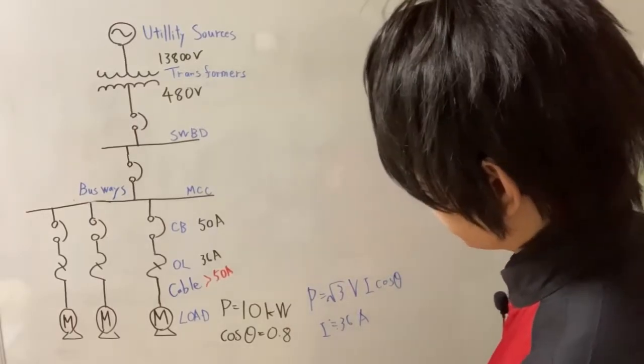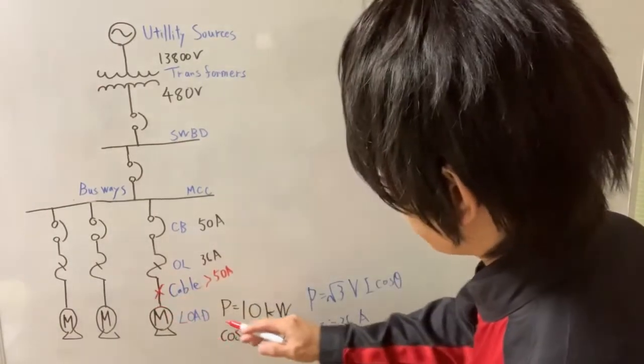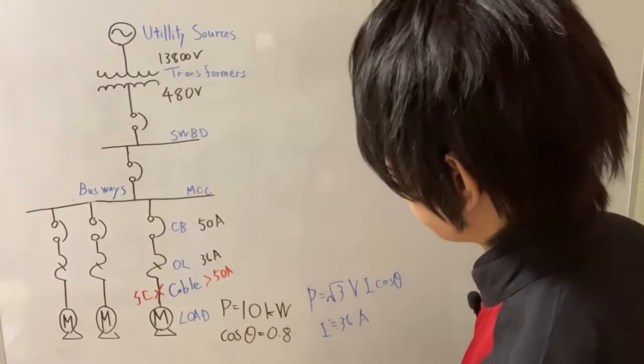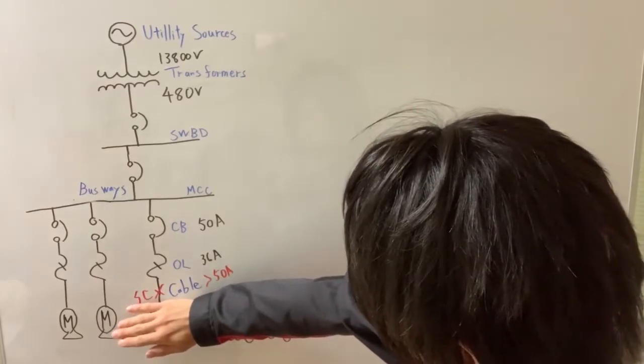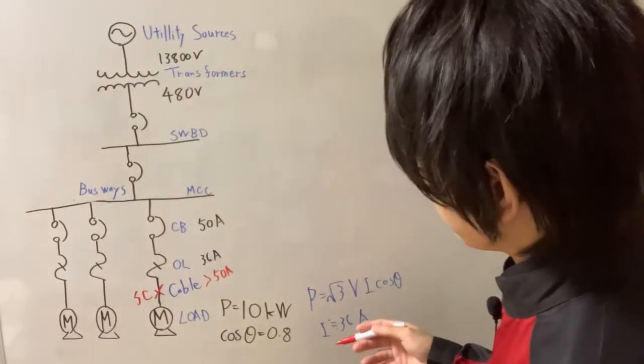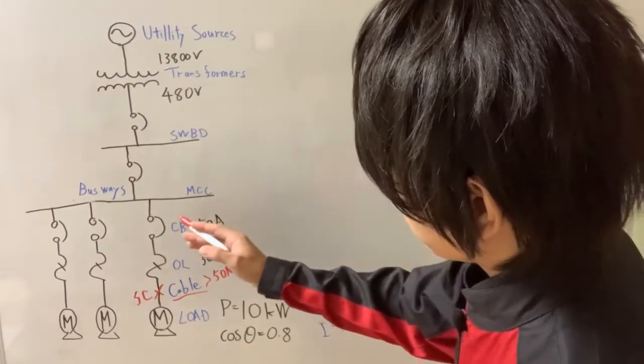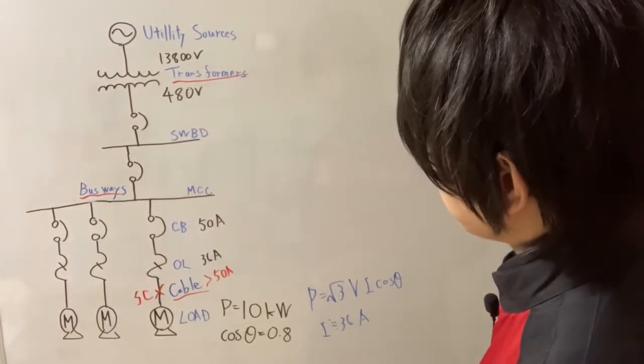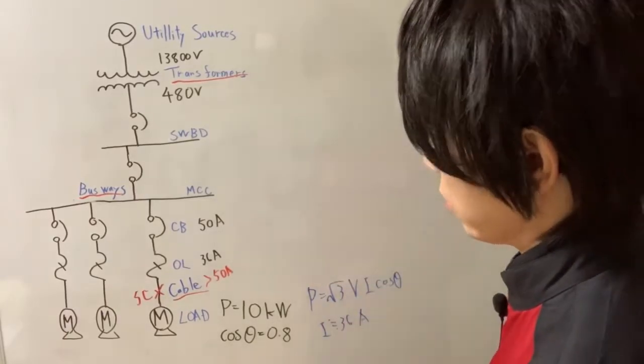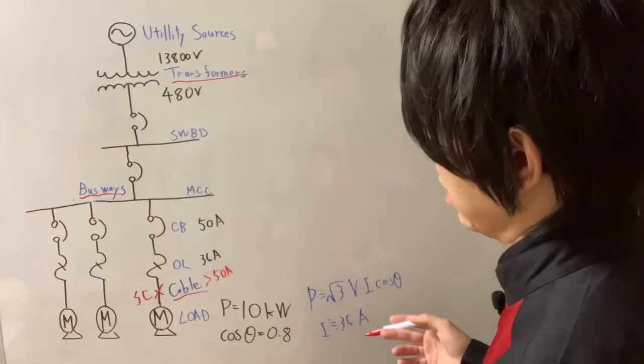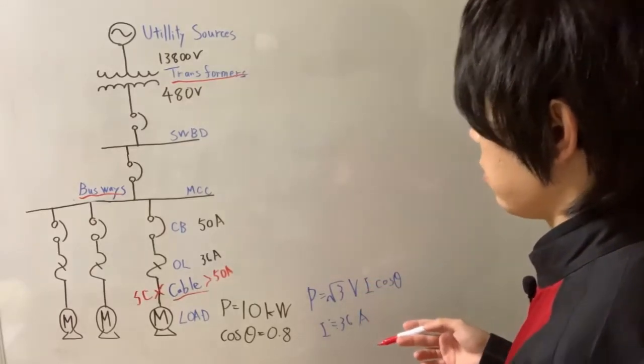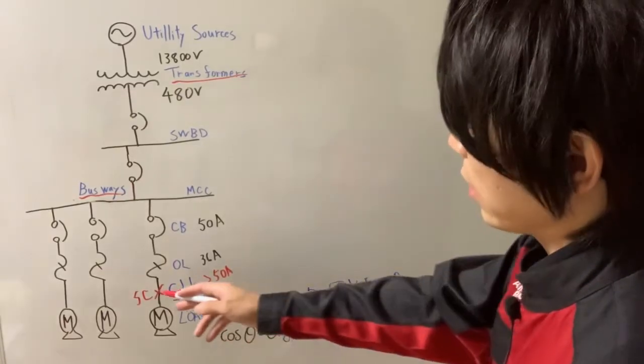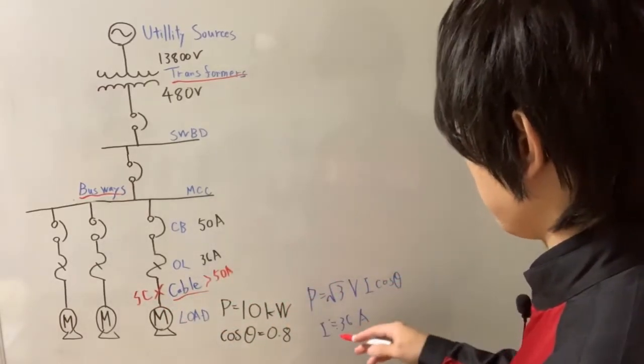So if short circuit occurs here, what will happen? You know, there are no load anymore. There are only impedances like cable or busway, transformer and so on. And the impedance of these devices is quite small because they are conducting devices. They are designed to not disturb the flow of the current. And that is why short circuit current is much greater than the normal load current.